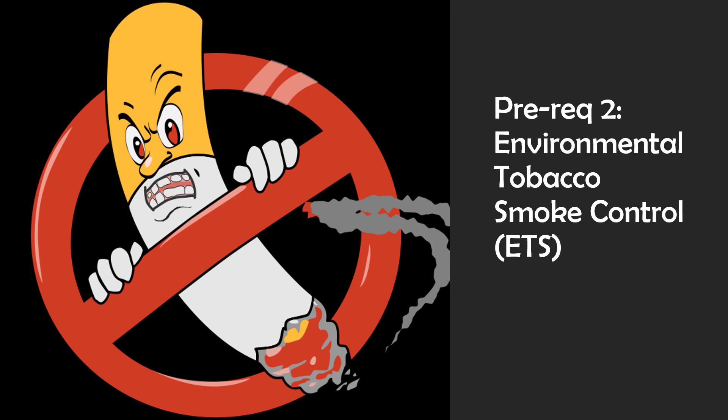Prereq two is no smoking. You need to prohibit smoking inside the building and prohibit smoking outside the building except in designated smoking areas located at least 25 feet from all entries, outdoor air intakes, and operable windows. You also need to prohibit smoking outside the property line in spaces used for business purposes. Signage must be posted within 10 feet of all building entrances indicating the no smoking policy. Smoking includes tobacco smoke, smoke produced from the combustion of cannabis and controlled substances, and the emissions produced by electronic smoking devices. Be sure you know the distance requirements.